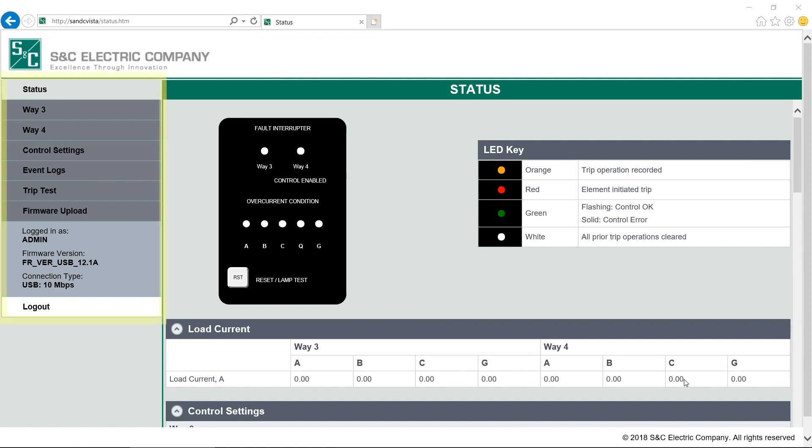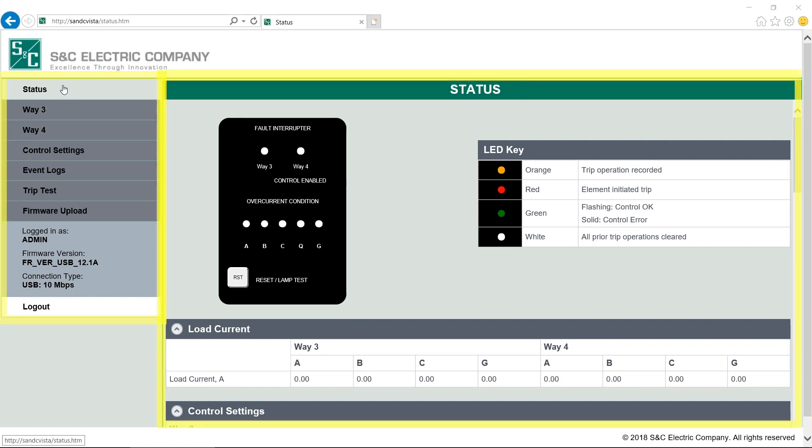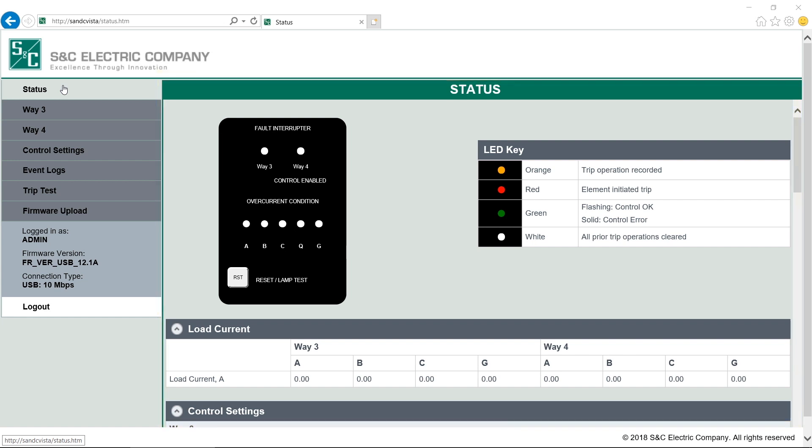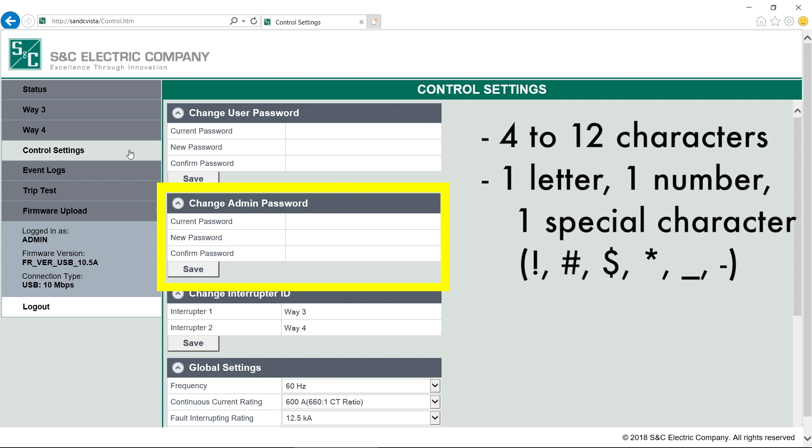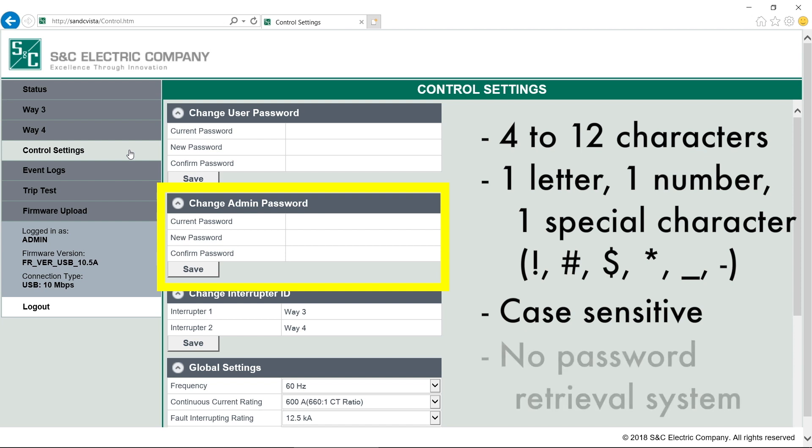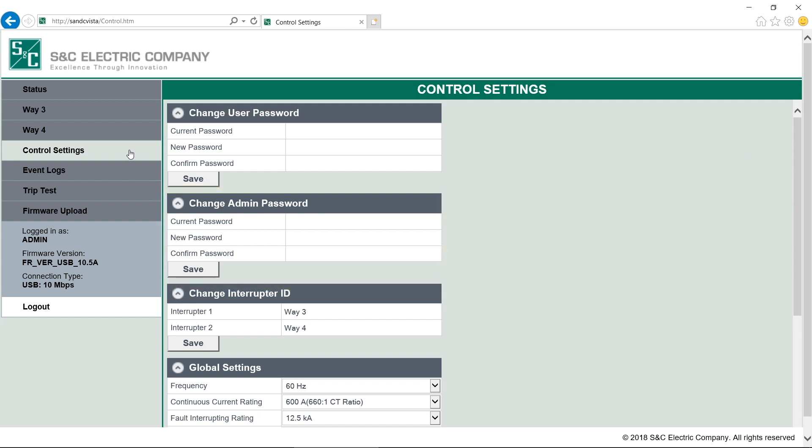After logging in, you'll see this menu down the left side and information for that menu in the middle. The first thing we'll do is reset the Admin Password. Navigate to the control settings, and from there, just follow the standard form to create a new password. The password must be between 4 and 12 characters, with at least one letter, one number, and one of these special characters. Keep in mind, too, that both the username and password are case-sensitive. It's very important that you do not lose the password. For security reasons, there is no password retrieval system built into the overcurrent control. If the Admin password is lost, the control must be returned to S&C Electric Company to restore access to the control.